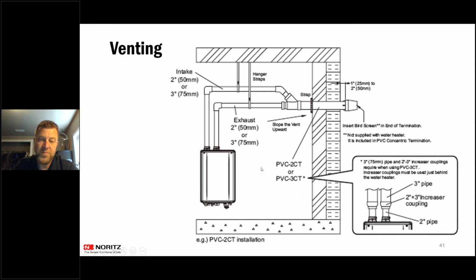So if you are coming off the top of our unit, like our EZ and our NRCR units, it is 2-inch connections up there on top. So if for some reason you are upping it to 3-inch, you would just put a small piece of 2-inch pipe and then a 2 to 3 inch coupling or reducer. We ask that it is a belled reducer versus you putting a bushing into a coupling, because if you do it with that bushing in there, it could cause pooling of condensate on top of there. So we always ask that it is a bell reducer if you are going to be reducing it from 2 to 3.